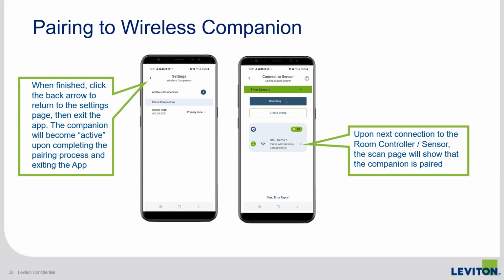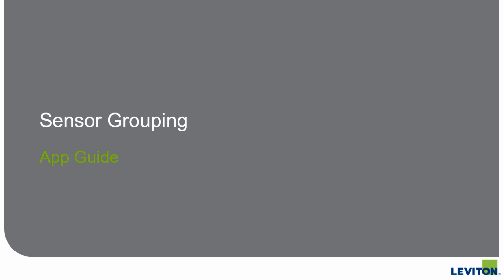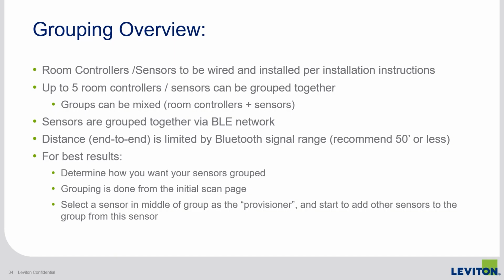Next, we'll show you how multiple sensors and/or room controllers can be grouped together to expand the occupancy sensing coverage. Up to 5 sensors and room controllers can be grouped together. The group can be mixed, which means a 0 to 10 volt dimming room controller can be grouped with a switching only sensor. Certain functions will be limited to the sensor since they are on-off only, where the room controllers have 0 to 10 volt dimming capabilities.